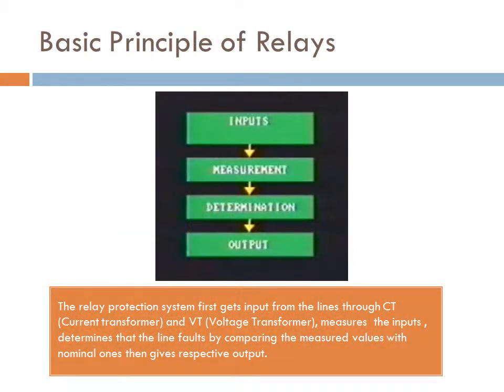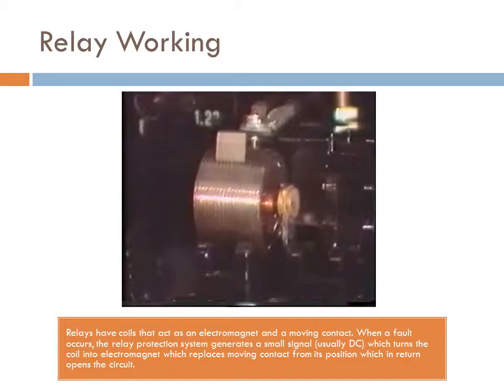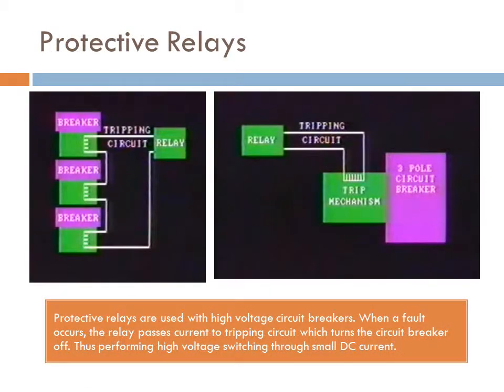The basic principle of relay is that it first takes the input from the lines through current transformer and voltage transformer, measures the input and determines whether the fault occurs or not. If the fault occurs, it sends a signal to circuit breakers. Protective relays are used with high voltage circuit breakers. When a fault occurs, the relay passes current to tripping circuit which turns the circuit breaker off. In this case, only one relay is used. If the relay does not work, it can damage the whole system.